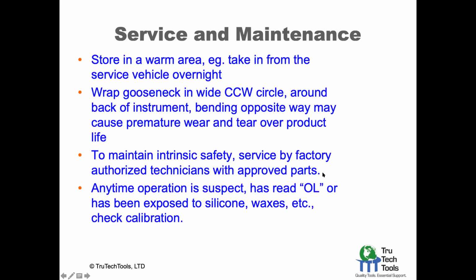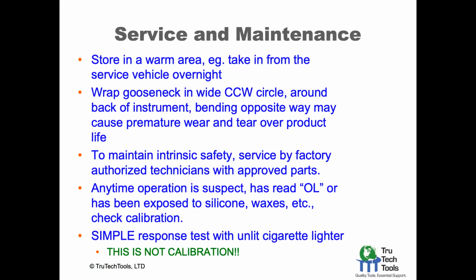And anytime you have an overload reading or you've exposed it to silicones or waxes, you want to check the calibration. That means, like, if a floor has just been buffed, something like that, these compounds can actually coat the surface of the sensor and not allow it to react with the combustible gases. So that gets into a dangerous situation. A simple response test is to take a lighter and just flick it, not the flame, but just the gas only. This is not calibration, but this is a response test, sometimes in the industry called a bump test. You're just bumping it, nudging it, like that person sitting next to you right now who's falling asleep. You bump them just to see if they're awake and alive.